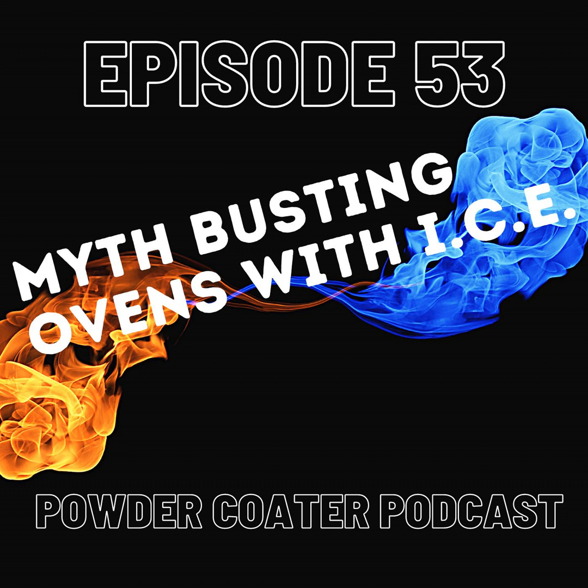We use a Rockwool mineral insulation. On all our powder coat ovens, all our walls are 6-inch thick. On dry off, for economics, we'll use 4-inch. But the rule of thumb, typically with rock wool, is 1 inch for every 100 degrees. You kind of use that as a rule of thumb, and that gets you in the realm. That's why we use 6 inch, because even though we design it for 425, somebody's going to run it at 450, and in your heater house you're hotter than that, because in a gas fired oven you'll see a difference of anywhere from 50 to 100 degrees.